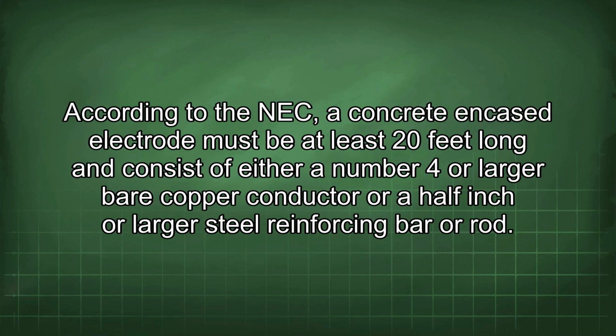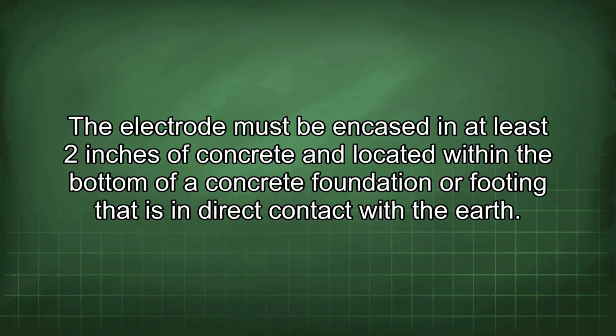According to the NEC, a concrete encased electrode must be at least 20 feet long and consist of either a number 4 or larger bare copper conductor or a half-inch or larger steel reinforcing bar or rod. The electrode must be encased in at least 2 inches of concrete and located within the bottom of a concrete foundation or footing that is in direct contact with the earth.